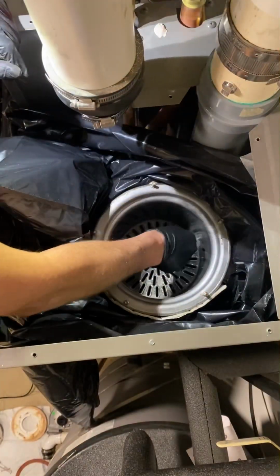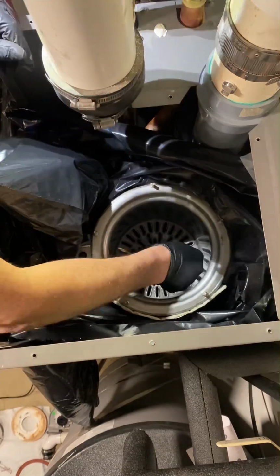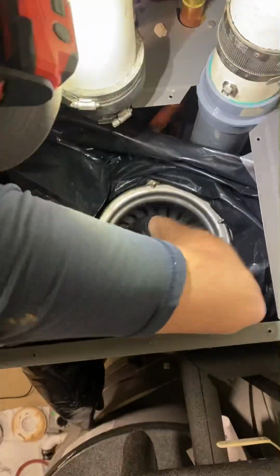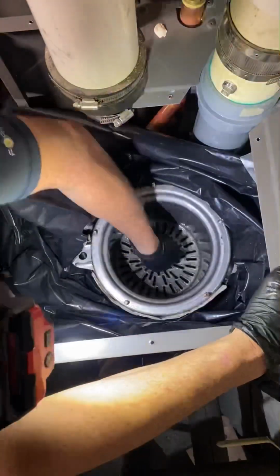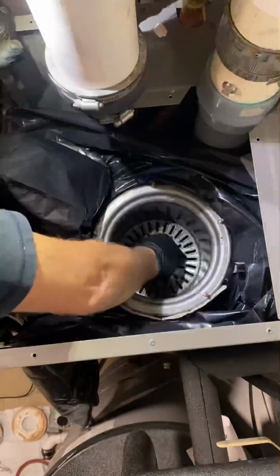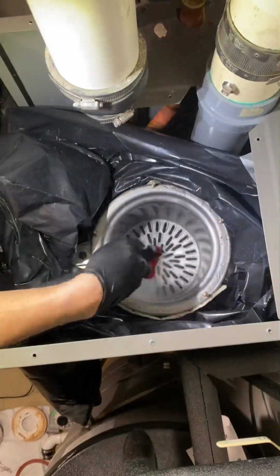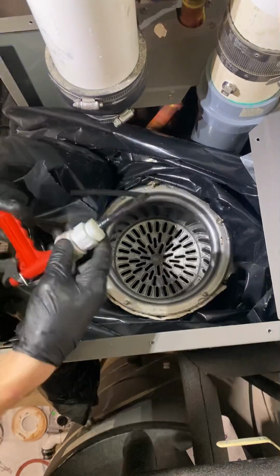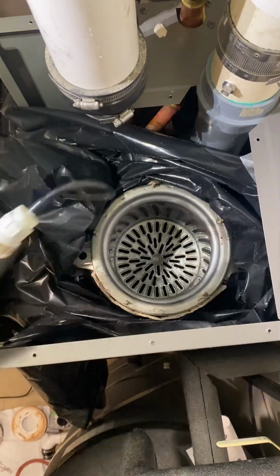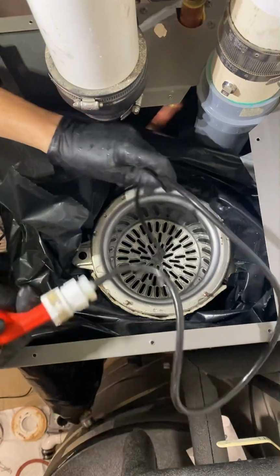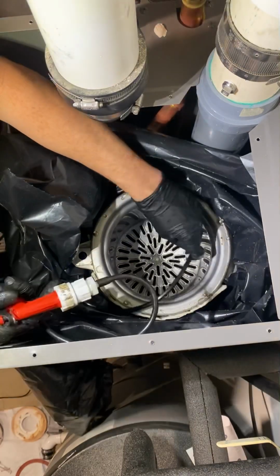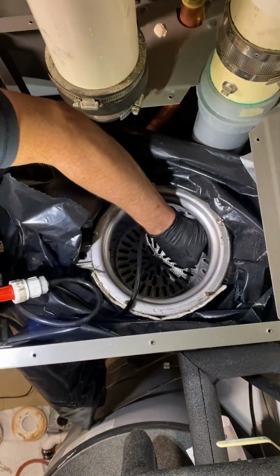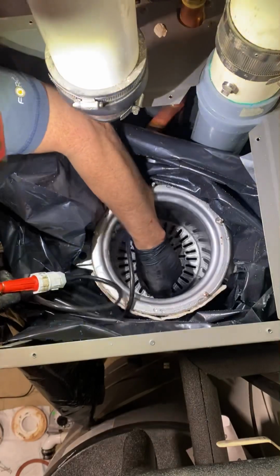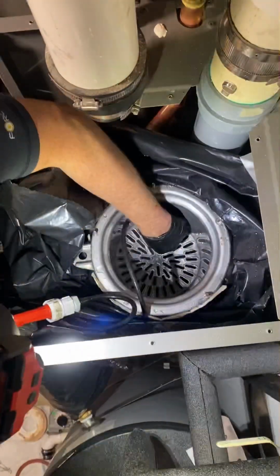You can use a small bottle brush to clean the fire tubes as far down as you can reach. This part of the job can be a little tedious. Patience is a virtue. Alright, now we rinse thoroughly with clean water. Hopefully you've already removed the condensate trap and placed a bucket below the condensate drain. For just a few bucks, you too can have one of these nifty high pressure water jets designed specifically for blasting out fire tube boilers.